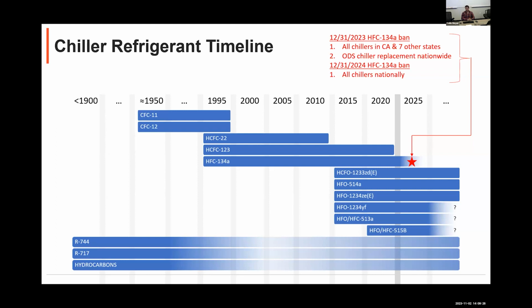Given the lead time of chillers and heat pumps in the market right now, lead times are looking at about a year. So if you were looking for a refrigerant with a GWP of 700 or above, it would need to be put on order almost immediately. Pretty soon we can just put all this behind us. There's been a lot of change, but we're at the end of the possibility of seeing refrigerants with a GWP of 700 or higher. So that means 134A and a lot of other HFC refrigerants are no longer going to be allowed in new chillers.